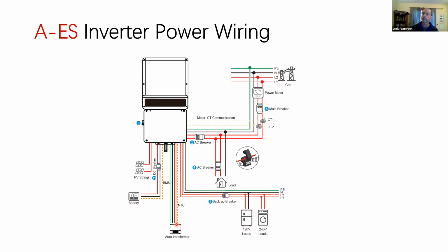So if you have an essential loads panel that has a 120 bus bar and another 120 bus bar, and for some reason people are using only the loads on one bus bar in a backup situation, it isn't a problem. It can be imbalanced. If you're not using an auto transformer, then you have to worry more about balancing. That's why this is an ideal solution for essential load backups.